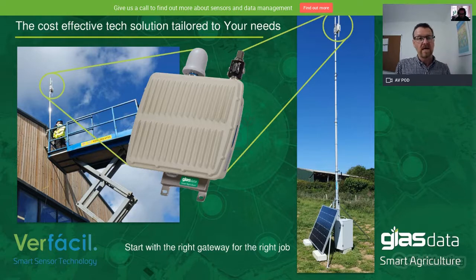The actual antenna itself, the central hub, which you can see in the middle of the slide and also top left there, the central hub for the sensor data flow to the internet and to the dashboard, is the LoRaWAN gateway. This device is typically located at a building that provides both power and internet. We look for tall buildings to mount the external antenna, and that gives us many miles of range. For indoor applications, we use a small router. It looks like a broadband router, and it's a simple 5-minute installation. And for projects where there's no power and no internet connection available, we've got a completely autonomous solar-powered unit with its own onboard 4G backhaul, and that's the image on the right.